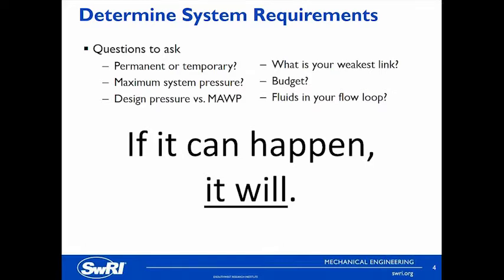The next question to ask is: what is your maximum system pressure? This is not really maximum allowable working pressure — there's a difference between design pressure and maximum allowable working pressure. You should design your system to comfortably operate at your design pressure. So if your weakest link in the setup is 2,000 PSI, then your design pressure shouldn't be 2,000 PSI — it should be something less, like 1,500 PSI. It's important to design to comfortably operate where you're going to be operating every day.